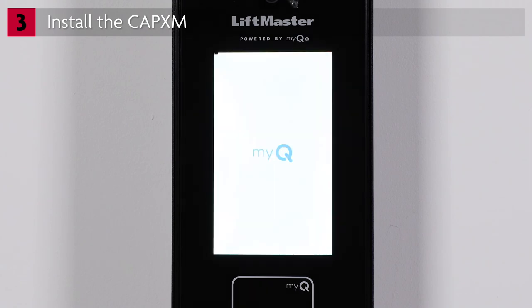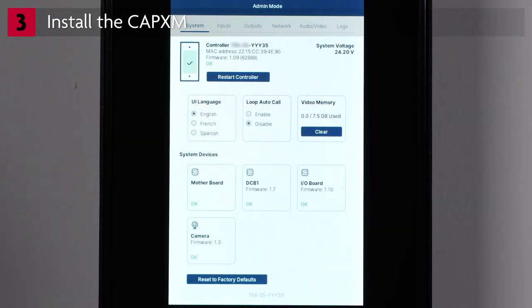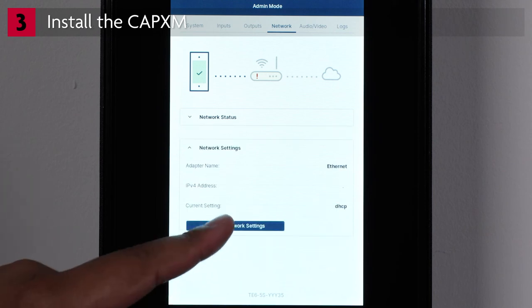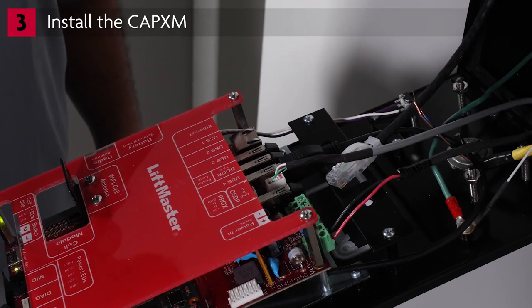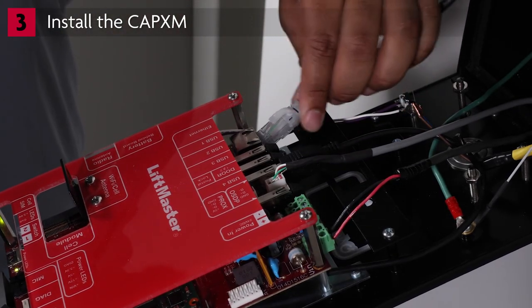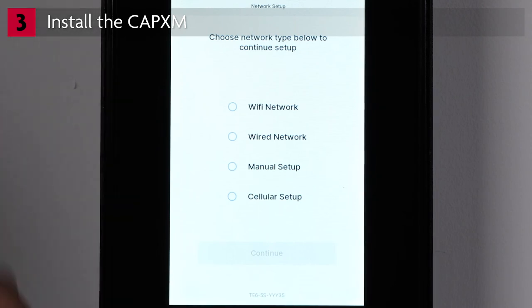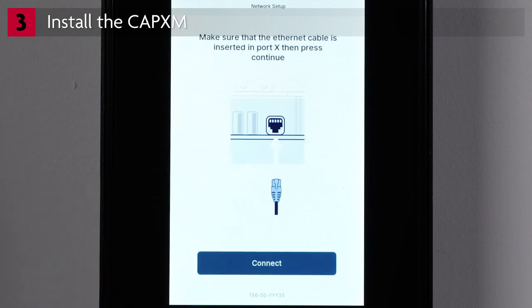The CAPXM will boot into admin mode. Let's get the network connection set up. Tap Network, then tap Change Network Settings. You'll be prompted to select the network type — there are three options: Wi-Fi network, wired network which configures automatically, and manual setup of a wired connection. If you're connecting to a wired network for automatic configuration (DHCP), plug in the Ethernet cable. Choose Wired Network and tap Continue. Connecting to the network may take a few moments. The network status will show Connected. Tap Connect.